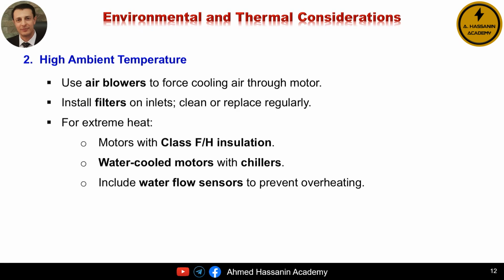Okay, now let's talk about motors running in hot environments. Think factories in the desert or anywhere the ambient temperature is high. Heat is a big enemy for motors because it stresses insulation and can shorten motor life. One way to deal with this is air cooling. Motors can be equipped with air blowers that force external air through the motor to keep it cool. But don't forget about filters on the air inlets. They need to be cleaned or replaced regularly. Otherwise, the airflow gets blocked and cooling becomes ineffective.